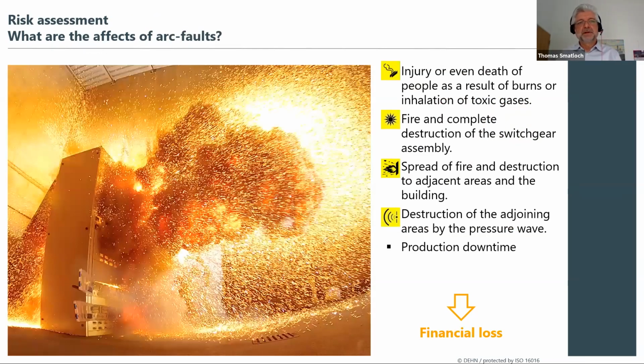Good. So let's speak about the effects of an arc fault. What can happen when a person is in the vicinity of this area? Of course, you can have serious injuries or even deaths of people as a result of burns or the result of the inhalation of toxic gases. When such an arc fault happens, some metals are vaporized, other parts will be vaporized, and as typical behavior of a human being, when such a shock appears, you typically inhale from this shock, and this is relatively dangerous, of course. When you inhale those toxic gases, this can kill you. And then we have fire and flames here, of course.